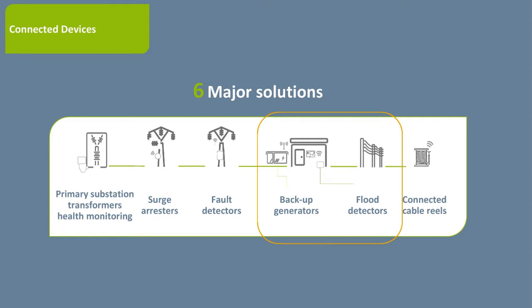Another example of interest is crisis management. I already talked about backup generators, so I won't repeat that, but it's helpful. We also retrofitted secondary substations with flood detectors. It's simple: you measure the water level in the building. You get notified, and can better coordinate efforts to cut power remotely if needed. When the flood recedes and water level drops, you're notified it came down, so field teams can be more efficient, go back, dry it out, and turn the power back on. These are IoT tools that are really helpful for us during crisis management.